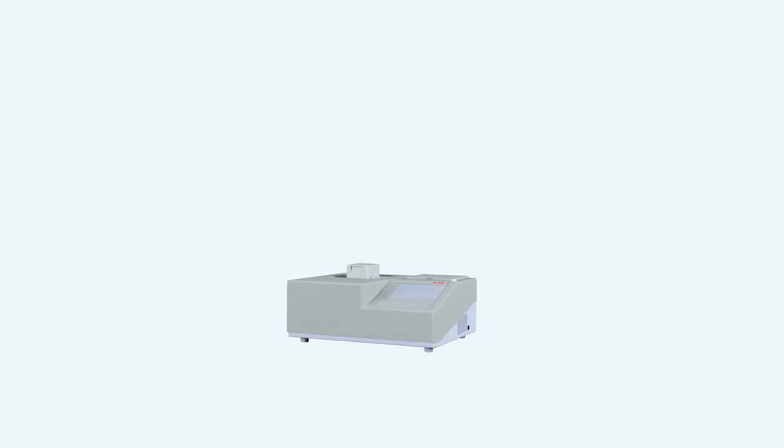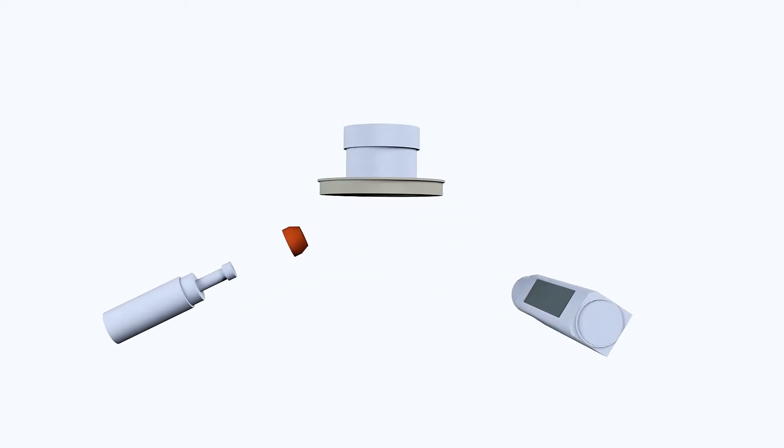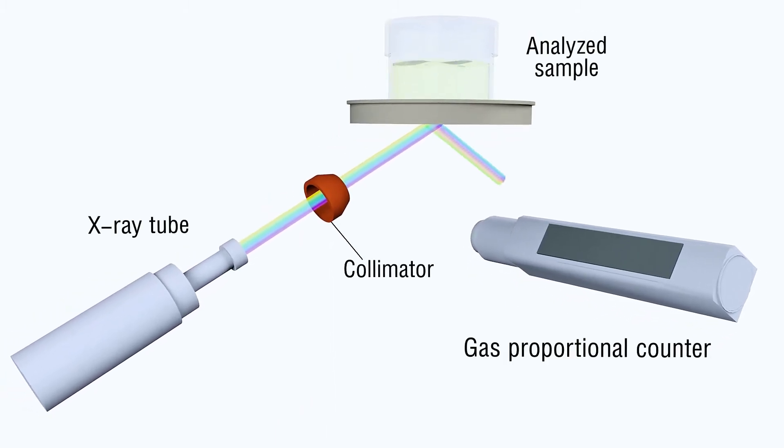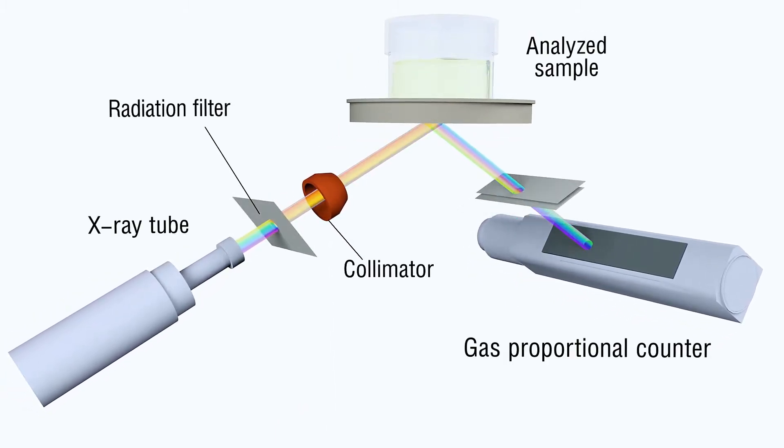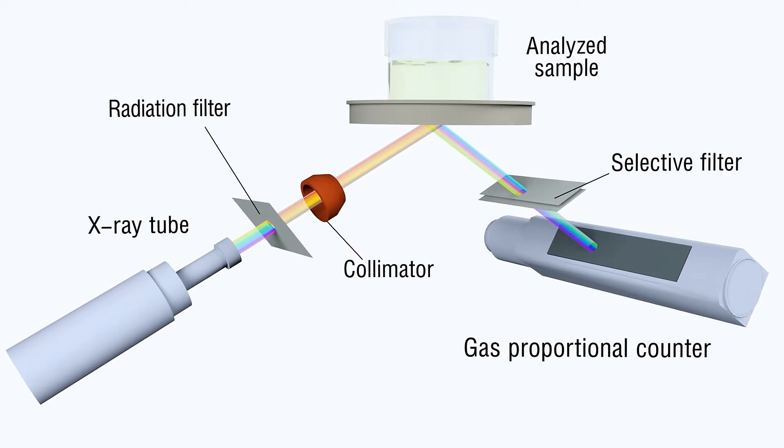The physical principle of equipment operation is based on measurement of fluorescent radiation intensity of sulfur in the analyzed sample and intensity of scattered X-ray tube radiation for matrix correction. The X-ray tube radiation excites secondary radiation in the sample, which is registered by a gas counter.